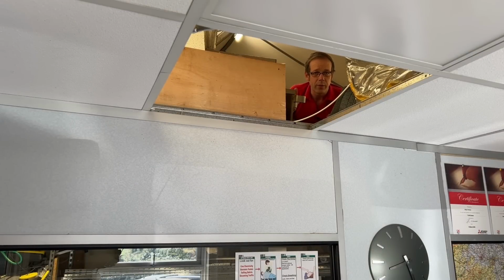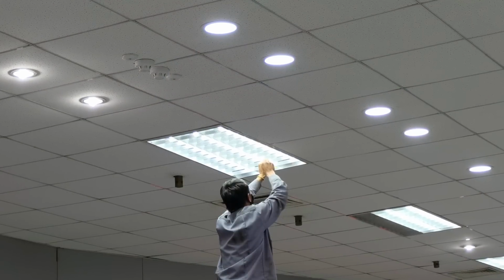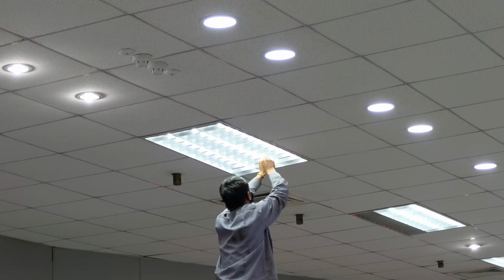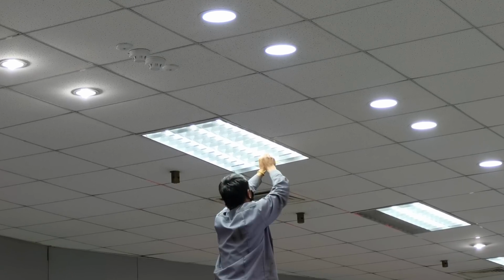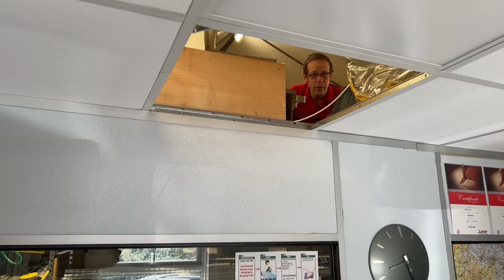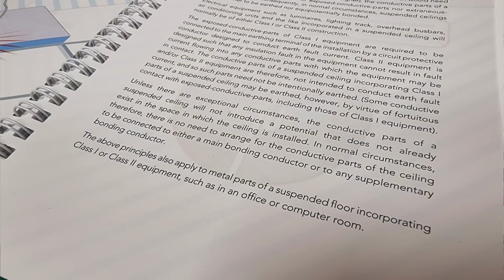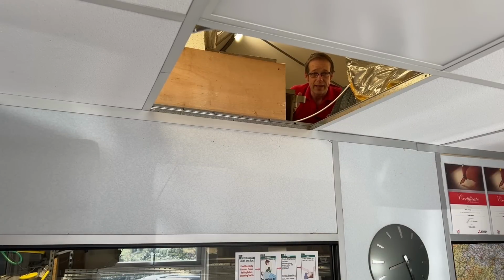What about Class 1 equipment though? A fault in that could lead to the metal casing becoming live, which, if it's resting in the ceiling grid, could then also become live. Well, maybe, but if the casing of the equipment is earthed as it should be, then the parts of the grid will experience earthing via what the Snags and Solutions guide calls fortuitous contact. It concludes by stating that in normal circumstances there is no need to arrange for the conductive parts of the ceiling to be connected to either a main bonding conductor or to any supplementary bonding conductor. So in short, the answer is, generally speaking, no, the ceiling grid won't need earthing or bonding.